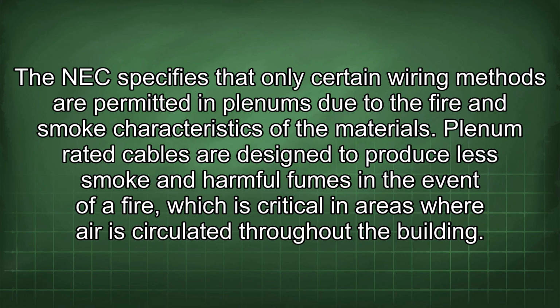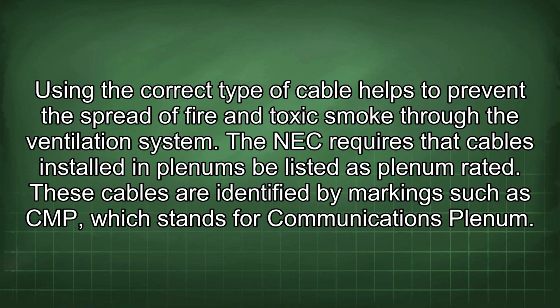The NEC specifies that only certain wiring methods are permitted in plenums due to the fire and smoke characteristics of the materials. Plenum-rated cables are designed to produce less smoke and harmful fumes in the event of a fire, which is critical in areas where air is circulated throughout the building. Using the correct type of cable helps to prevent the spread of fire and toxic smoke through the ventilation system.